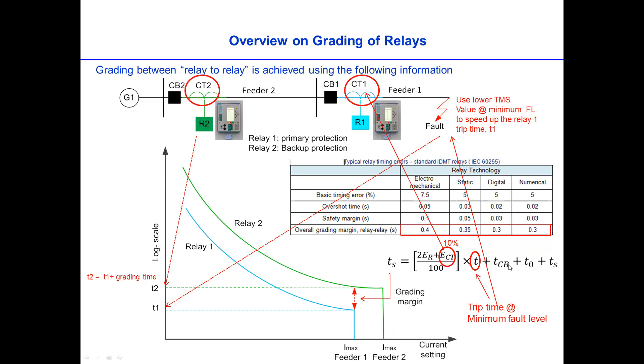And then the next one is what we need to know is the TCB. The TCB, the trip time of the circuit breaker, each circuit breaker we have. So we need to find out how much. Usually it is 50 milliseconds.